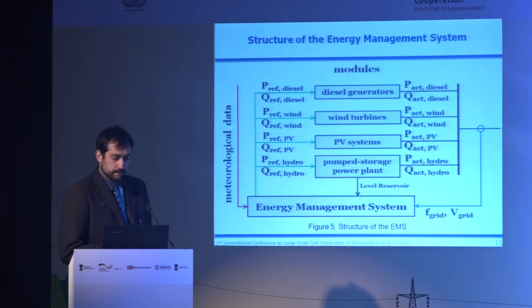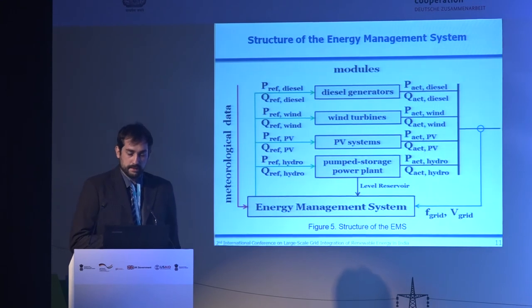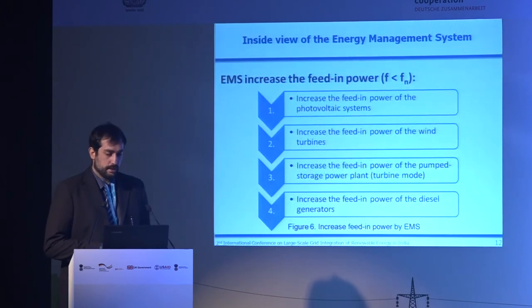Let's take a closer look at the management system. It collects information such as grid frequency, grid voltage, and importantly the reservoir level of the pump storage power plant — because if you are running out of water, you need to start diesel generators to maintain grid stability. The management system then sends reference values for active and reactive power to each of the generating modules, which feed power into the grid and provide frequency feedback to the controller.